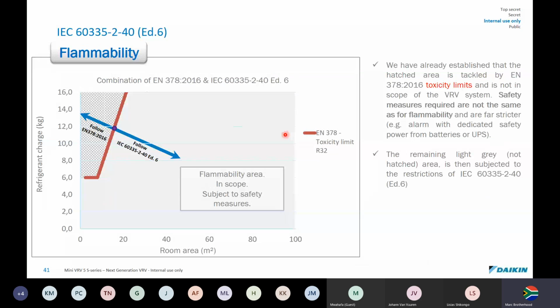Looking at flammability, and we're back to room area now, the size of rooms. We've already established that the hatched area has been tackled by the standard 378 toxicity limits and is not in scope of the VRV system. Safety measures required are not the same as for flammability and are therefore much stricter. So anywhere where there's a fire, these standards are much stricter. And what do they mean? Like you need an alarm with a dedicated safety power from batteries, etc. So they've said here that the remaining light grey area, and not the hatched area, will be subject to the restrictions. So the grey area is in scope, and this is what Daikin will be following.